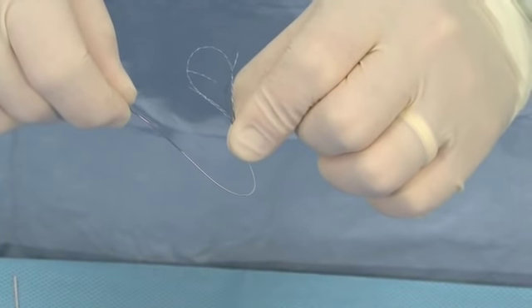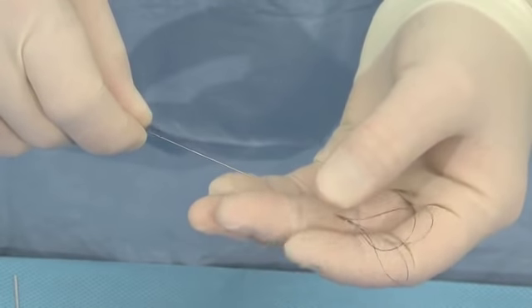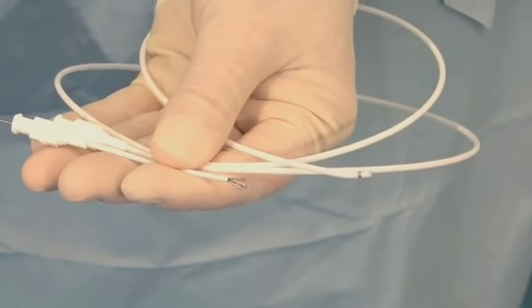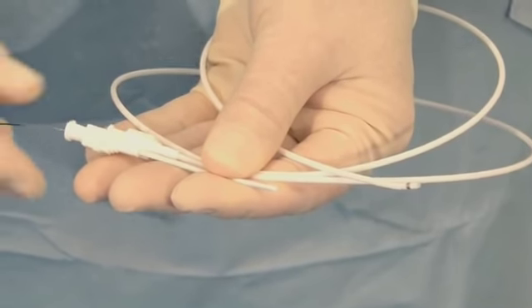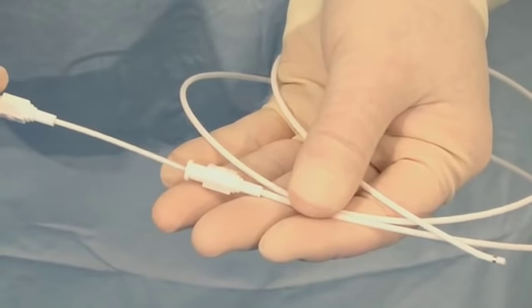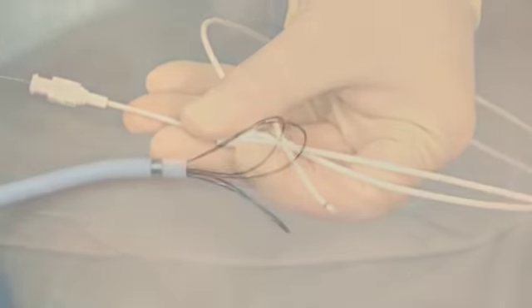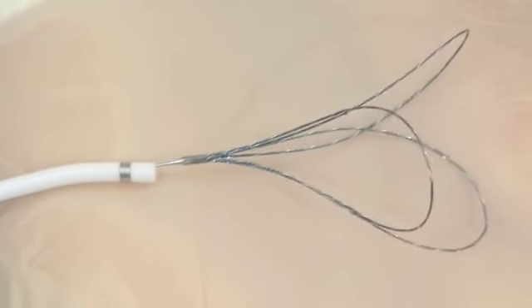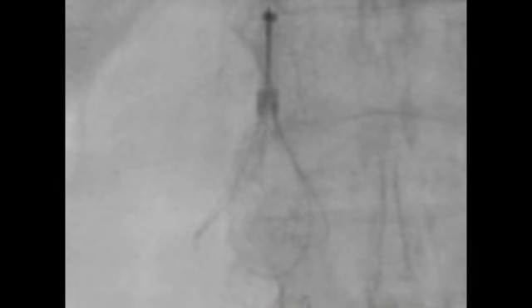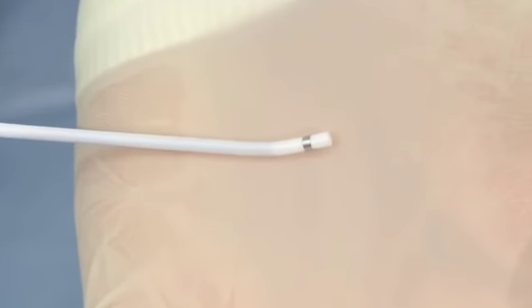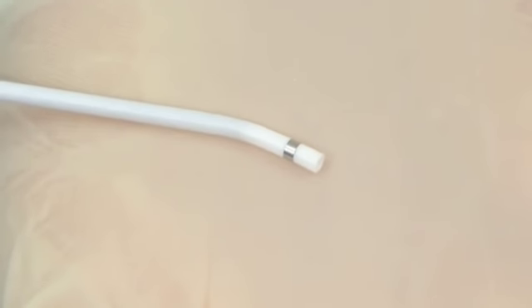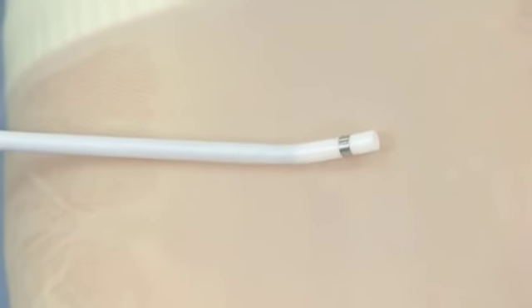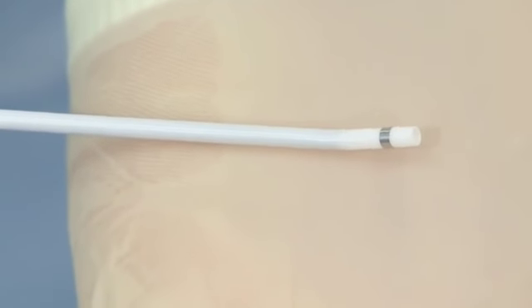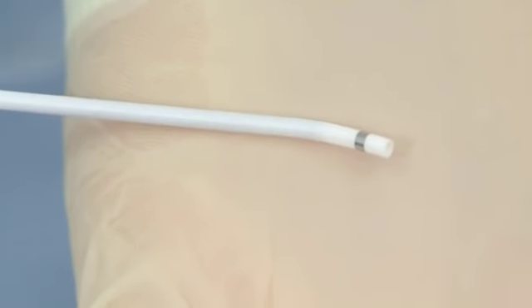The snare is constructed of flexible, kink-resistant, superelastic nitinol wire, enabling it to be introduced through catheters without the risk of device deformation. Platinum strands are incorporated in the snare loops for excellent fluoroscopic visualization. The Ensnare kink-resistant guiding catheter includes a radiopaque band that is easily visible during fluoroscopy.